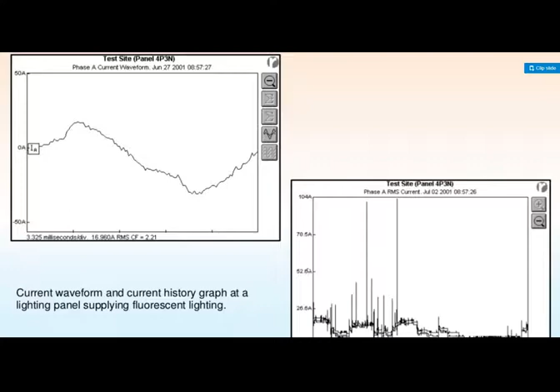Now, data loggers and chart recorders. Data loggers and chart recorders are sometimes used to record voltage, current, demand and temperature data in electrical power systems. They are slow response devices that are useful for measuring steady state data over a long period of time. These devices record one sample of the event at predetermined durations such as 1 second, 2 seconds, 5 seconds, etc. The advantage of the data logger is that it is relatively inexpensive compared to power quality recording instruments, and it is also easier to set up and use.